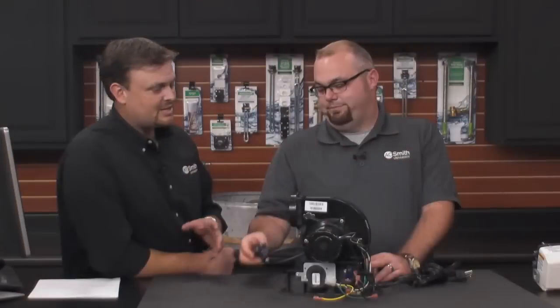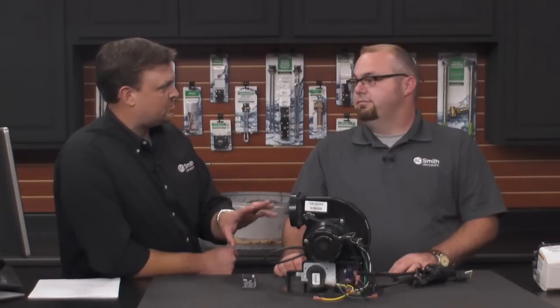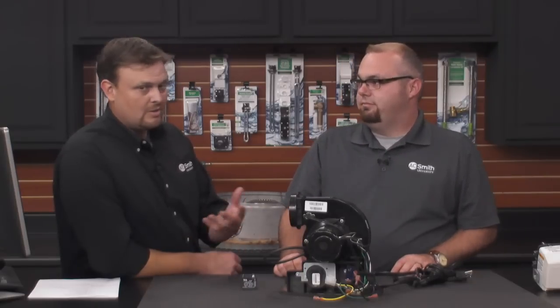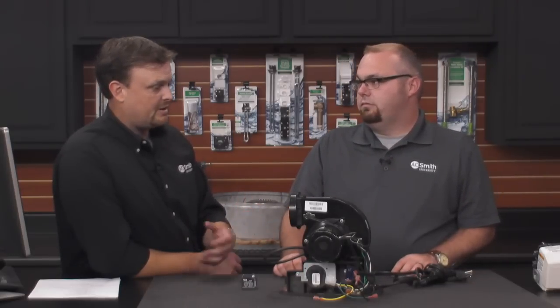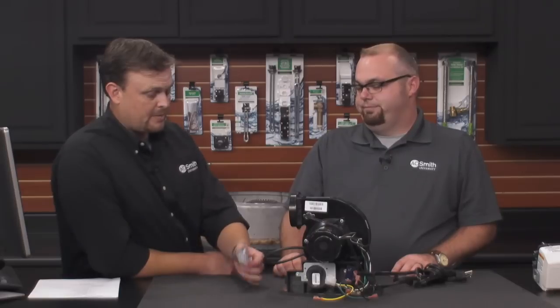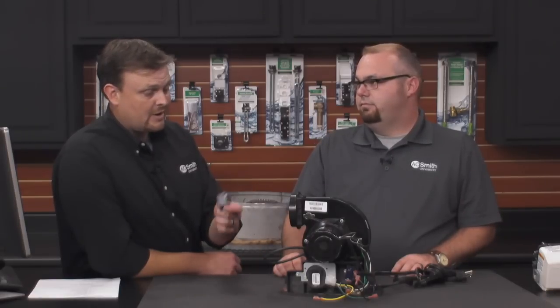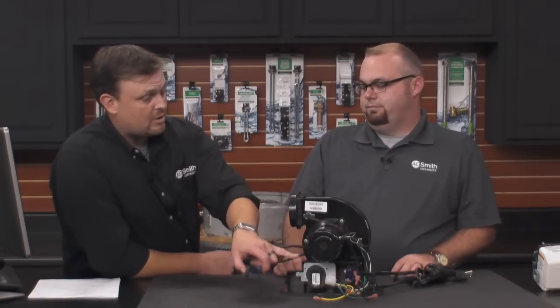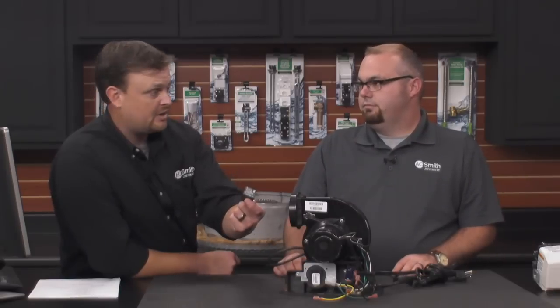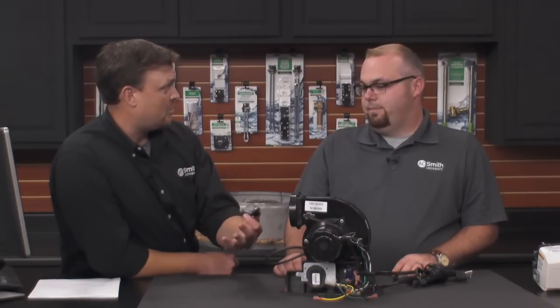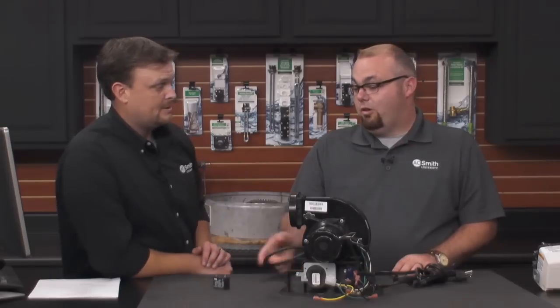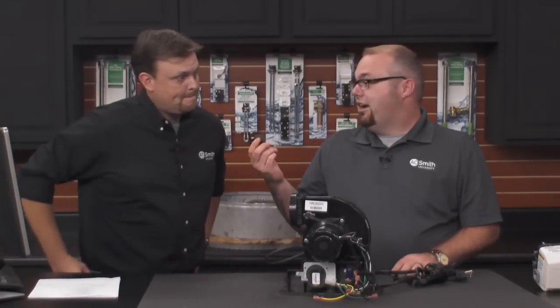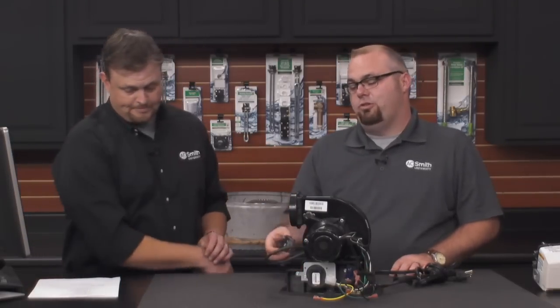Yeah, so that's great for service. If the blower won't start, normally with the older style, you'd have to replace the whole thing. Now we can just replace the capacitor. You can have one on your truck. Instead of pulling it off of the water heater, just unplug your leads, plug it into this, try it out. If it works, then go ahead and replace it. Correct, and most suppliers carry capacitors because several electric motors use these.